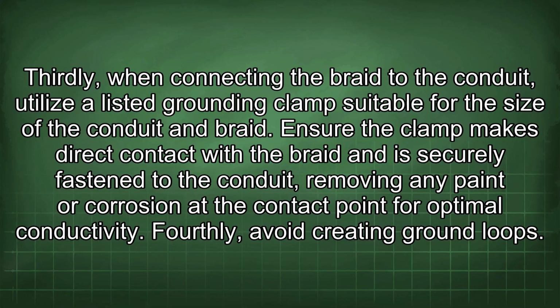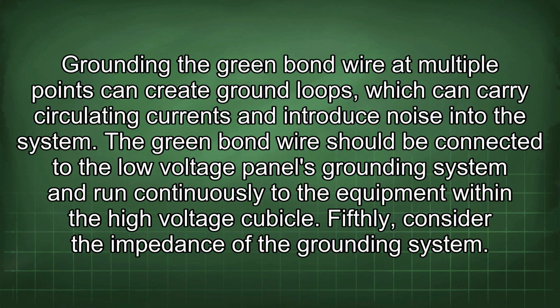Fourthly, avoid creating ground loops. Grounding the green bond wire at multiple points can create ground loops, which can carry circulating currents and introduce noise into the system. The green bond wire should be connected to the low voltage panel's grounding system and run continuously to the equipment within the high voltage cubicle.